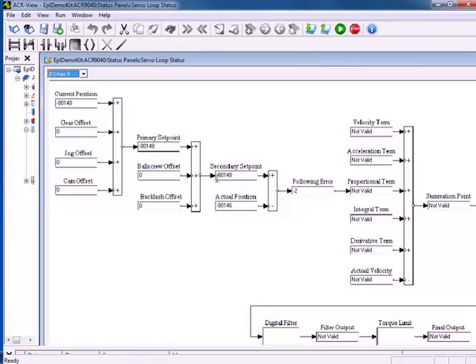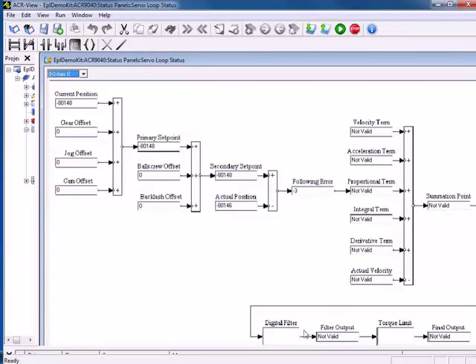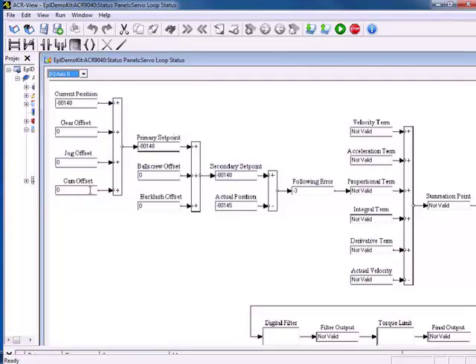We can see that our secondary set point and actual position are very close. We have a following error of two encoder counts. We don't have any additional proportional integral terms to be added for our summation point, no digital filtering or filter output, and no limit to our torque. So if you're getting motion and you think it should be stationary, come in here. It's possible that you have a jog offset set, something left over from a camming operation, or a ball screw offset input generating unintentional motion. Use this tool — it's very important when you're getting motion you don't expect or not getting the full range of motion that you would expect.